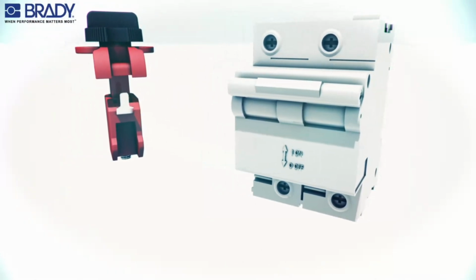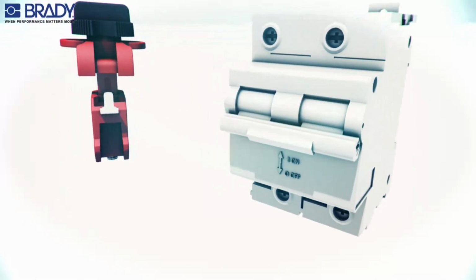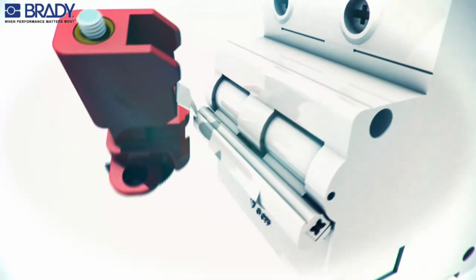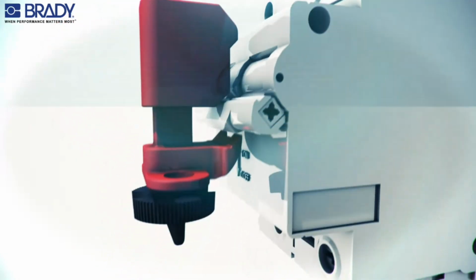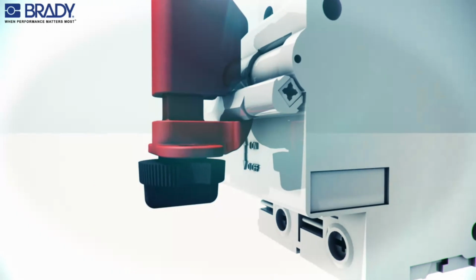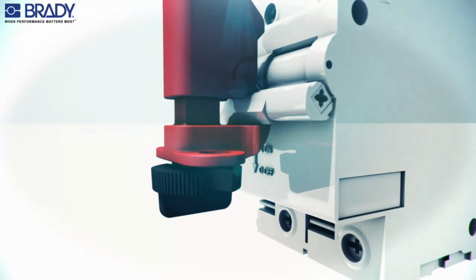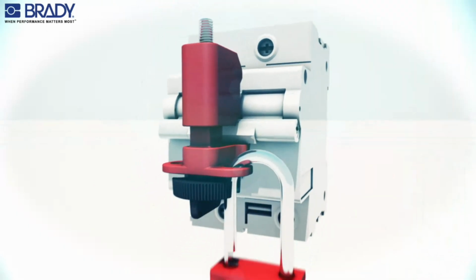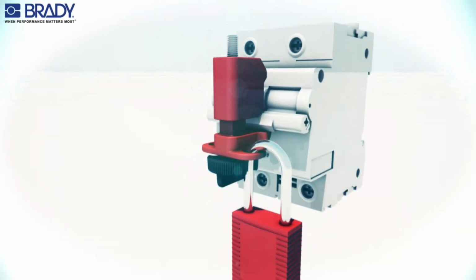Tie bar: place the circuit breaker in the off position. Put the metal clip under the tie bar and between the poles, then rotate the thumb wheel clockwise to secure the lockout device to the circuit breaker. Insert the padlock through the hole to secure the device in the locked position.